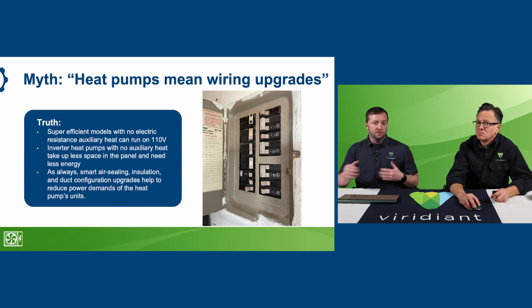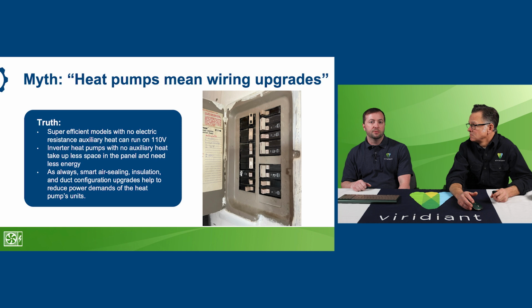And if physical space in the panel is a concern, there are some heat pump systems where the air handler inside is powered by the outdoor unit, so you can reduce the number of breakers that way as well. Of course, there will be those cases where a panel upgrade is needed, but it doesn't have to mean that a heat pump's not an option. There's a new 30% tax credit worth up to $600 for a new electric panel. And then there's what's called the HERA rebates, which include up to $4,000 towards a new electric panel.